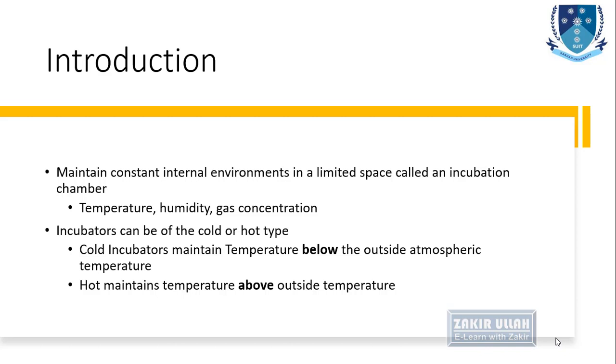Cold type incubators, we call them cold because we maintain the temperature below the outside atmospheric temperature. Usually these types of incubators maintain temperature below 22 or 20 degrees centigrade. As we know, the room temperature or the outside atmospheric temperature is around 20 to 30 degrees centigrade.